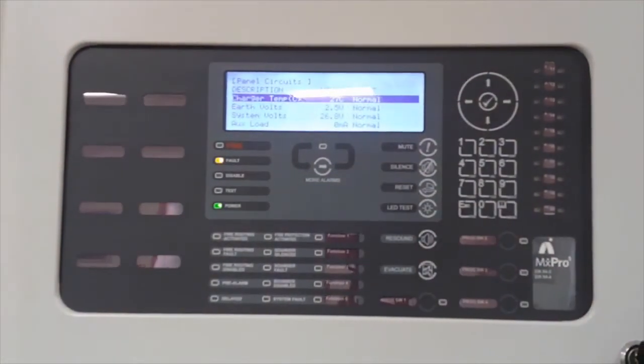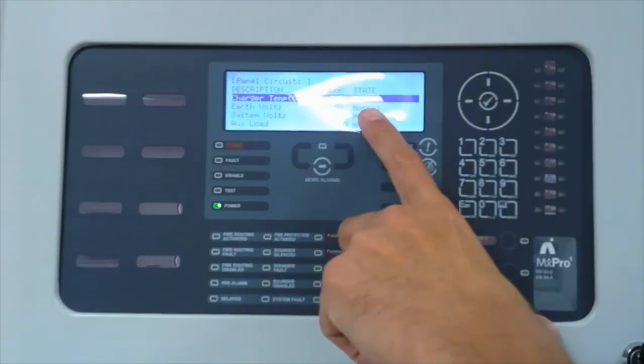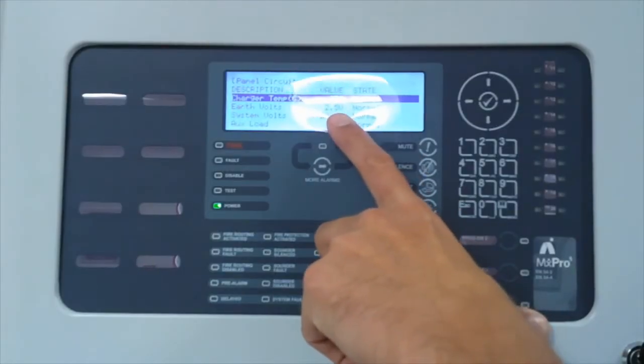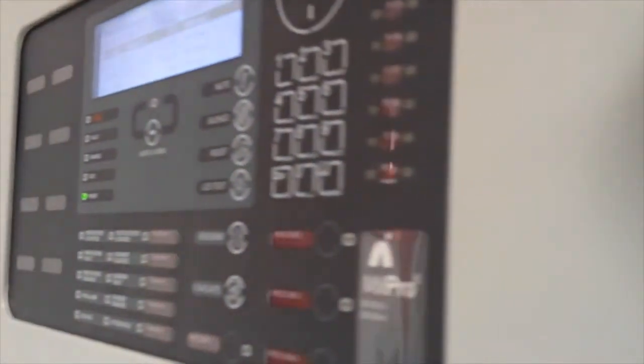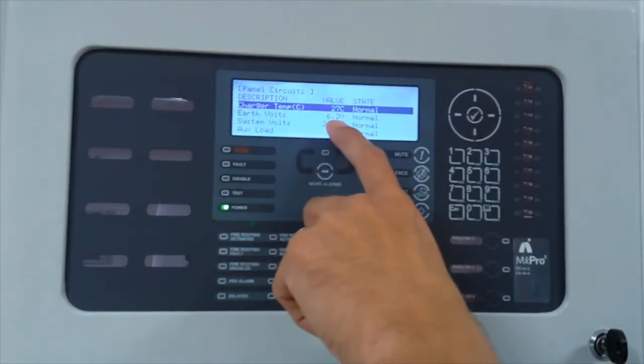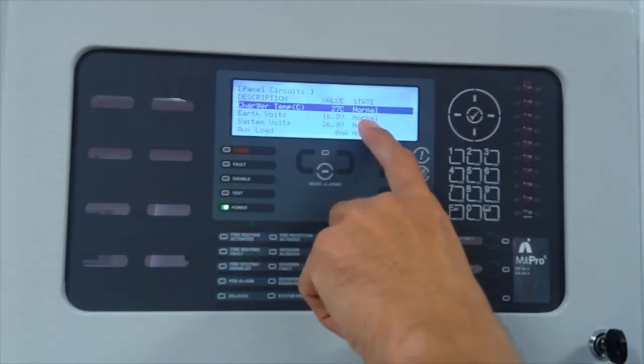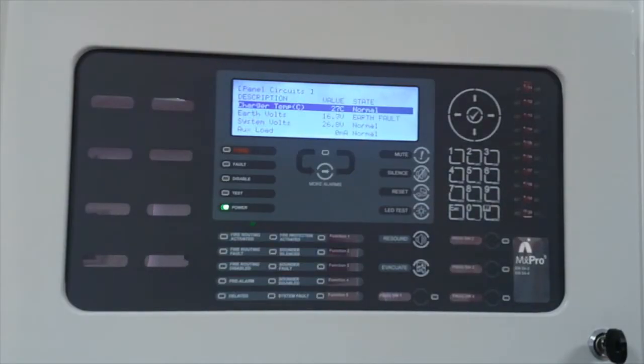If I unplug loop 1, you can see straight away, the fault is not latching, the fault is clear. So if I put loop 1 back in place, you can see my earth fault is creeping up again and it has gone into a fault.